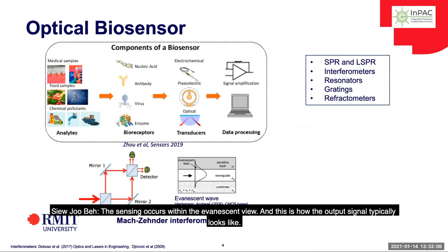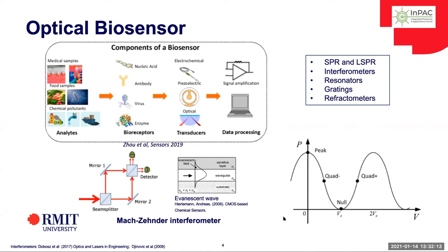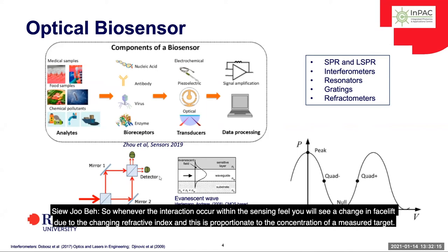The sensing occurs within the evanescent field, and this is how the output signal typically looks like. Whenever the interaction occurs within the sensing field, you will see a change in phase shift due to the change in refractive index, and this is proportionate to the concentration of the measured target.